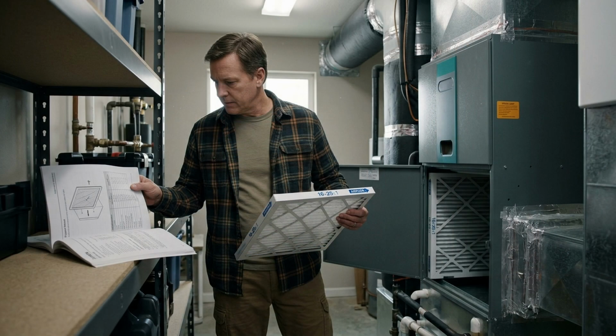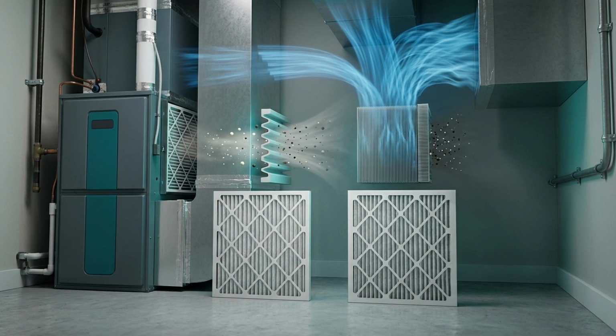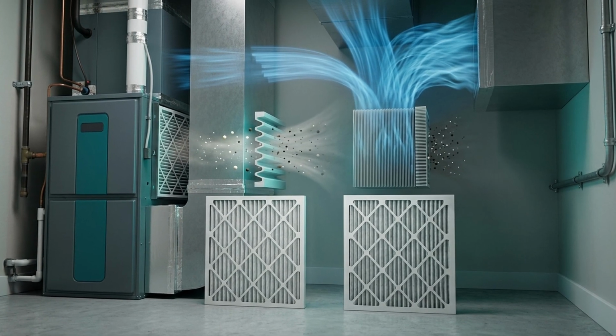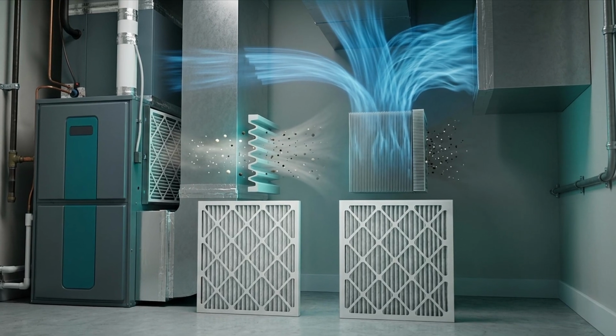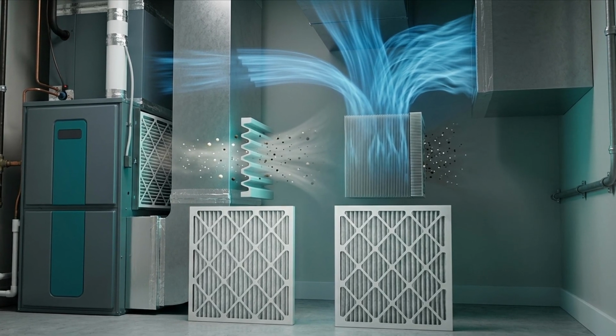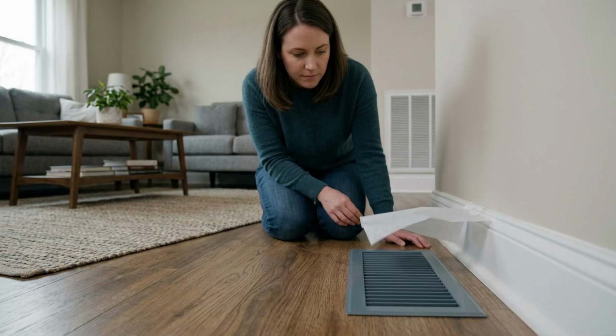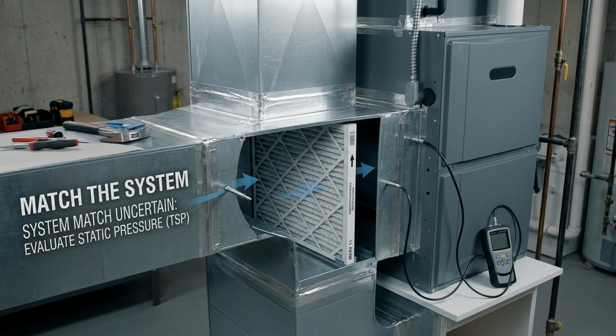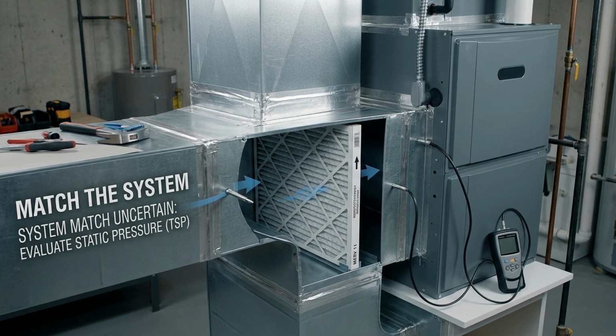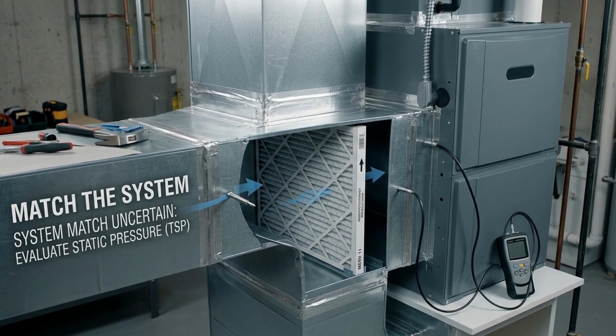Use a simple decision order. First, verify size, orientation, fit, and condition. Second, compare the exact filter's pressure drop information rather than assuming the MERV number tells the whole story. Third, watch for a repeatable comfort or sound change after installation. Fourth, if the system match remains uncertain, have airflow and static pressure evaluated instead of guessing.